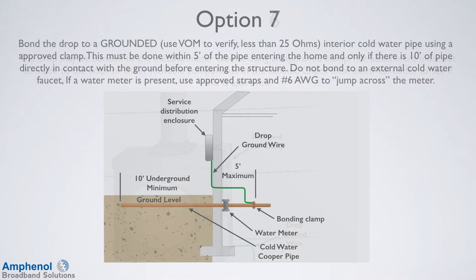On option number 7, the drop is bonded to a grounded interior cold water pipe using an approved clamp. This must be done within 5 feet of the pipe entering the home, and only if there is 10 feet of pipe directly in contact with the ground before entering the structure. You need to verify that there is 25 ohms or less of resistance to a ground in the house. If a water meter is present, use approved straps and a number 6 gauge wire to jump across the meter. Many cable TV companies no longer allow this practice as it's too hard to verify the 10 feet of pipe in the ground. Water meters have neoprene bushings, so a number 6 copper jumper would need to be installed to ensure continuity. Never bond to a black pipe (which is gas) or to an external cold water faucet.